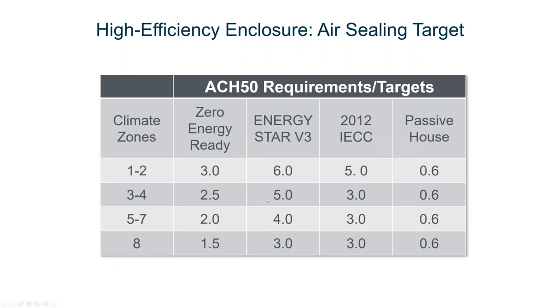On the air sealing side, the target we're trying to get to varies by program. From passive house, which is 0.6 air changes per hour at 50 pascals, you have all sorts of other levels. The code levels are 3 to 5. In 2012 IECC, ENERGY STAR varies from 3 to 6 depending where you are for version 3. And Zero Ready is right around half of the ENERGY STAR requirements. However, my personal recommendation is you really should be at 1.5 air changes at 50 pascals — almost anywhere you build in the country. Everyone should be at 1.5 ACH50 or better, no matter where you build a home.